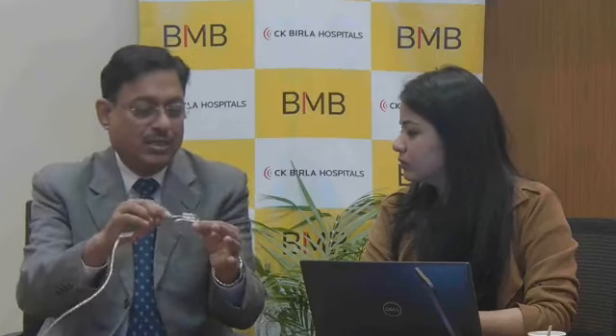The batteries are actually sealed inside. So you will see this is a hermetically sealed unit. You cannot take the battery out of it, because if you have something which can be taken out, this may leak into the body as well. We don't want that to happen ever. Right. So this is hermetically sealed. So when you need a change of battery, we have to change the pulse generator itself. So we disconnect the lead, which was connected here inside.